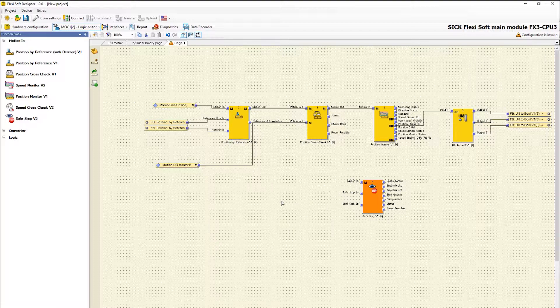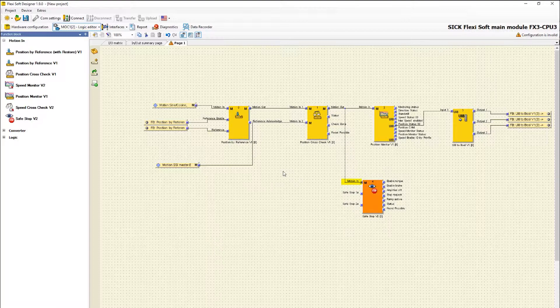First we focus on the relevant inputs and outputs. From the input Motion In, the function block receives all information provided by the encoders. In this context, I want to connect the output Motion Out from the function block Position by Reference with the input Motion In of the function block Safe Stop. The inputs Safe Stop 1 and Safe Stop 2 are able to trigger the relevant safety function.